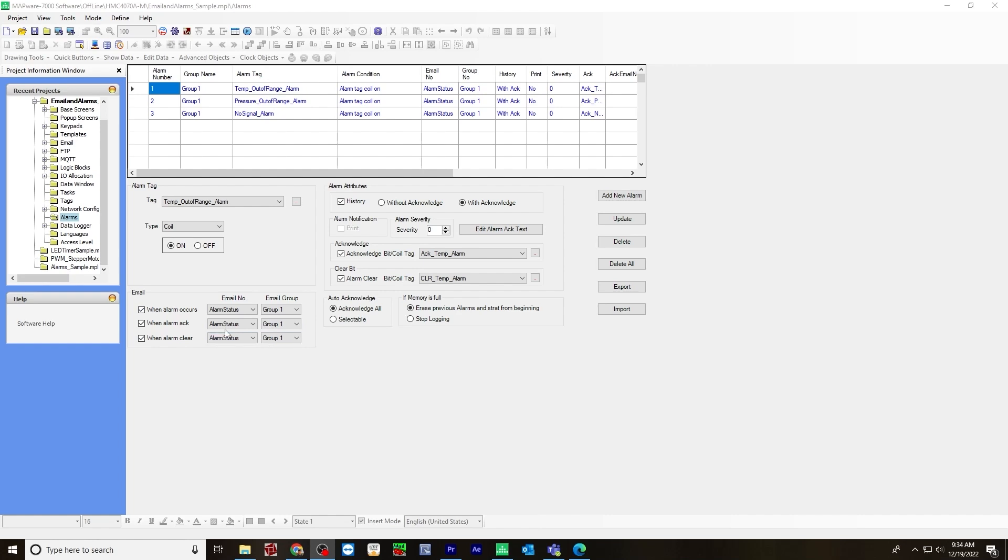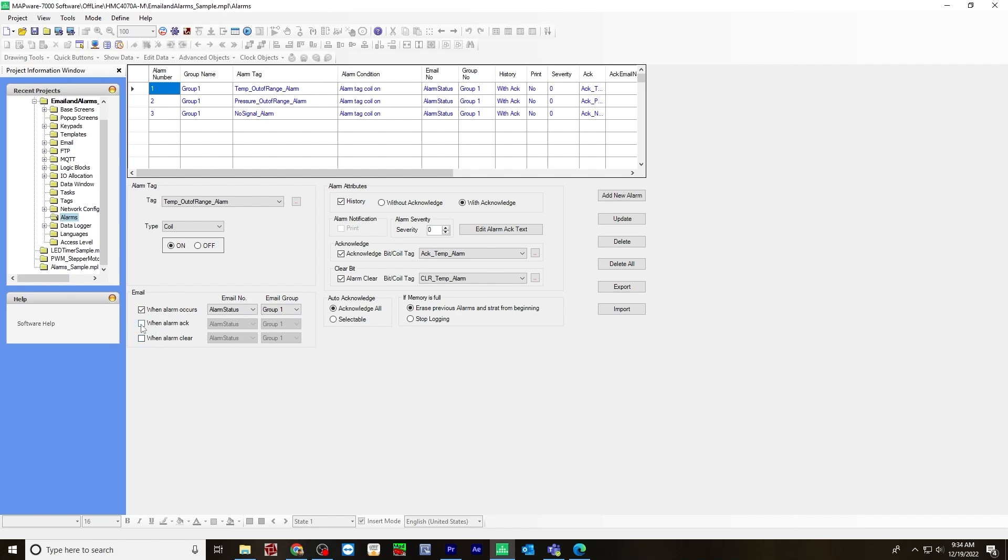So over to the left, I checked off when alarm occurs, alarm status, which would be that alarm screen we set up earlier on, email group will be group one. And here you can either just do when alarm occurs, or you can check these off when alarm is acknowledged and when alarm is cleared.